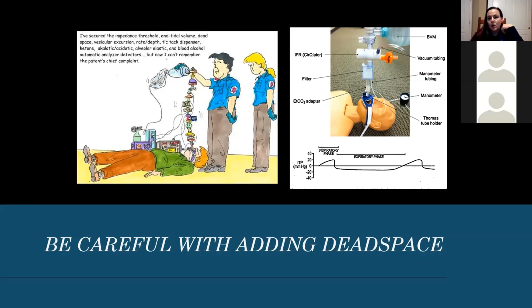I would say one expiratory filter, and I would say put it as close to you, to the caregiver, as possible, farthest away from the patient on the expiratory side. That'll decrease your chances of ruining that filter inside of there, and more chance for it to protect you, and your end tidal. I would say those are your 2 minimums. Sometimes I've even seen bigger end tidals, like adult end tidals used for babies, and sometimes I've even had to take those out. But for most of our adult patients, I would say your end tidal and your expiratory filter are your absolute 2 must-haves.